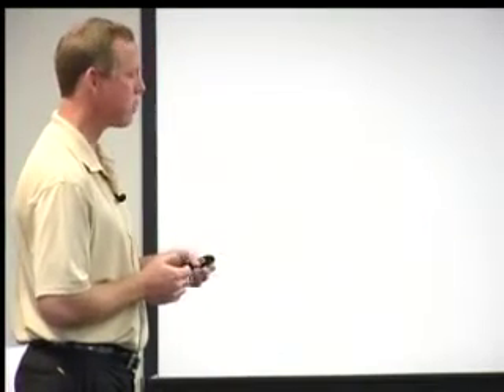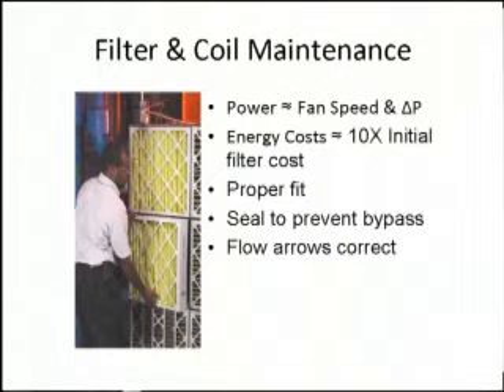And it's kind of a revolutionary air filter, and I'm not endorsing it, but I can tell you that we use it at UCF now quite a bit. It looks just like these filters, but it has a built-in electrostatic charge. And so what they are able to do is make this filter media more porous, where it has a lower pressure drop across it, which translates into more energy savings for us. But at the same time, the electrostatic charge allows it to still remove the particulates of a finer filter. So we're getting the clean air without having the bigger pressure drop.